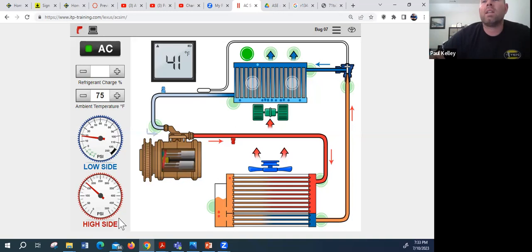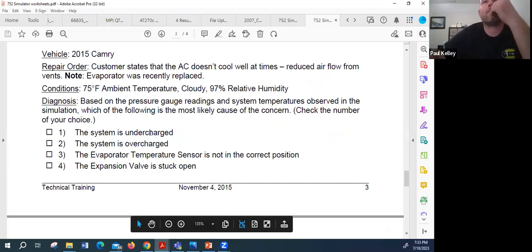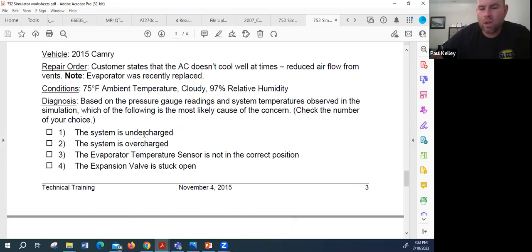Now, why did it freeze over though? That's kind of where we're at on this. It could be undercharged, but that doesn't really cause freezing. It could be overcharged, but that doesn't cause freezing either. This would be a low, and this would be a high. Instead, we're looking at the evaporator temperature sensor not being in the correct position, or the expansion valve being stuck open.